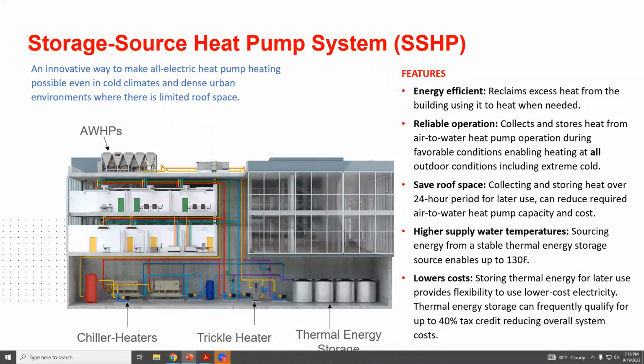Energy efficiency: we're talking about COPs. If we talk about air source products only, at low ambient of 0 degrees, we might see a coefficient of performance in the high 1s or low 2s. With water source heating products, where we're generating a lot of the heat via the ice, building ice and pulling heat out using water to water products, we might see COPs up in the 3s or 4s depending on temperatures created. So you're talking about an increase in overall system efficiency by creating better conditions for your equipment to operate in.